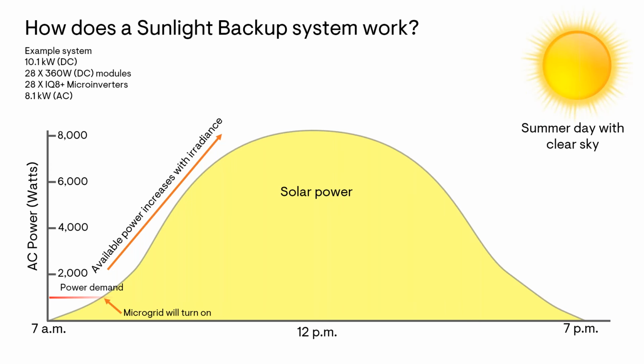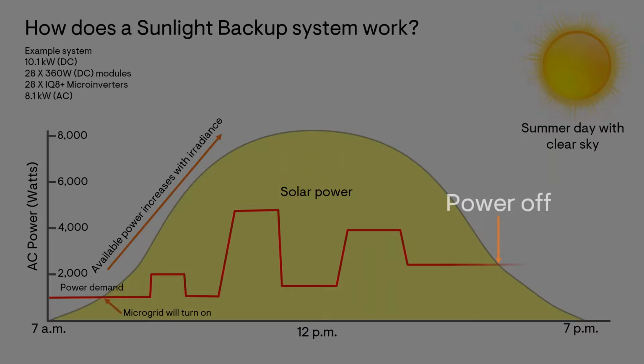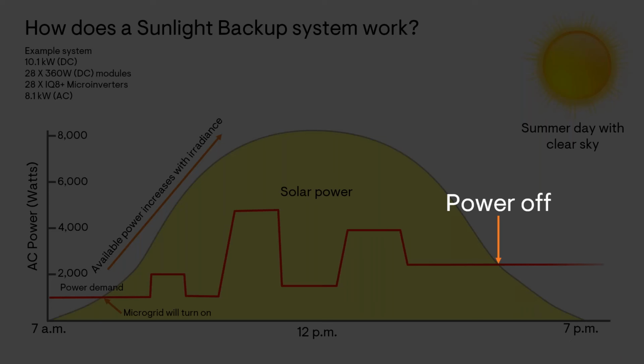When the sun rises, the microgrid will power up. The IQ system controller will disconnect from the grid. If the system can produce enough power for the electrical loads, the microgrid will stay up. But if the loads exceed the available power, then the system is going to shut down, and obviously the power will go out for that homeowner.